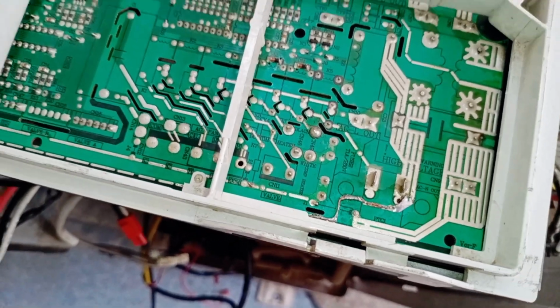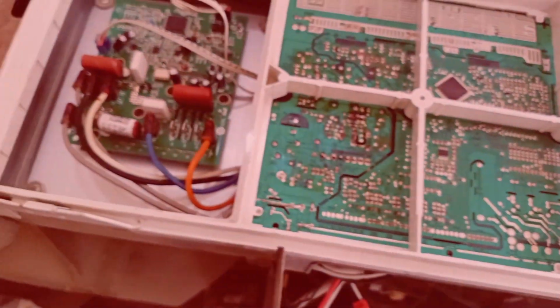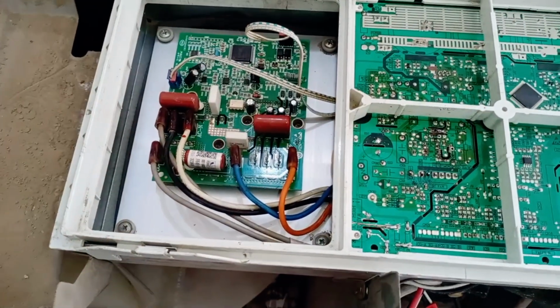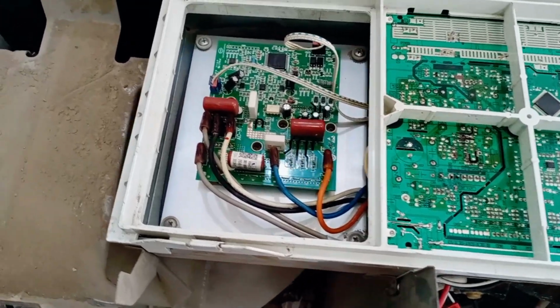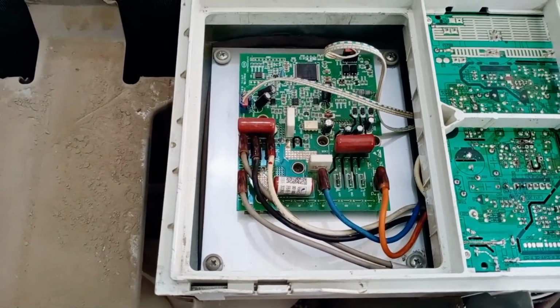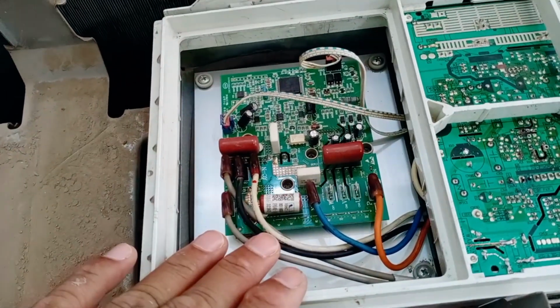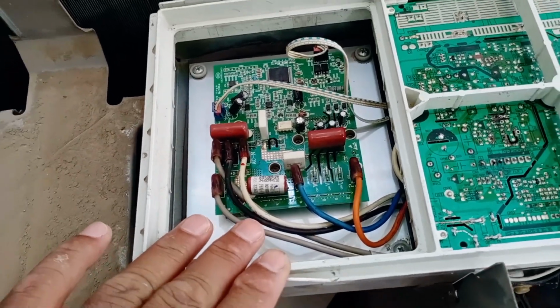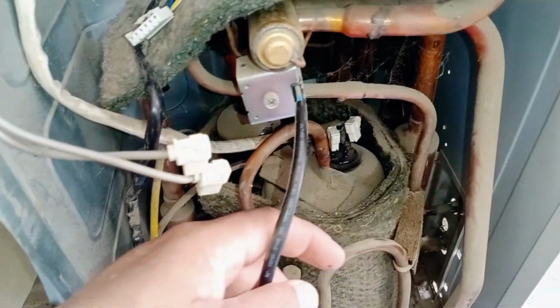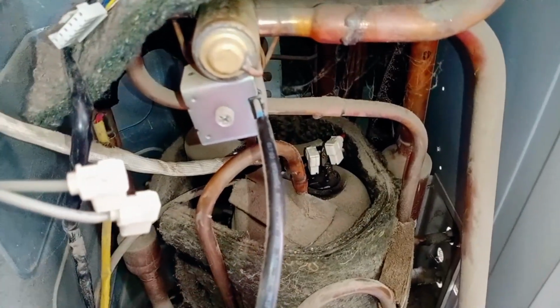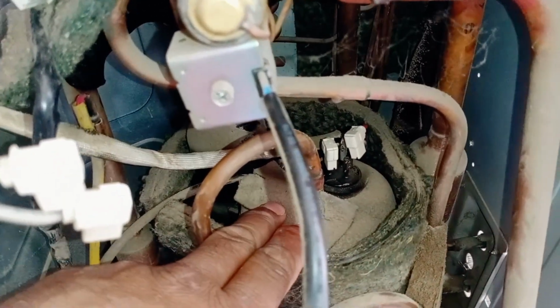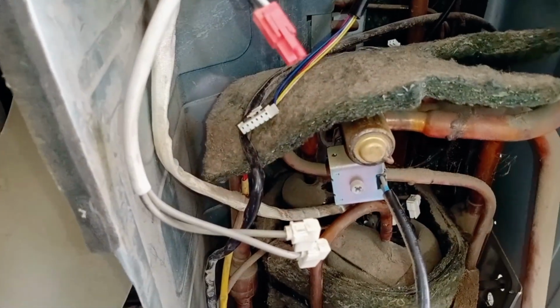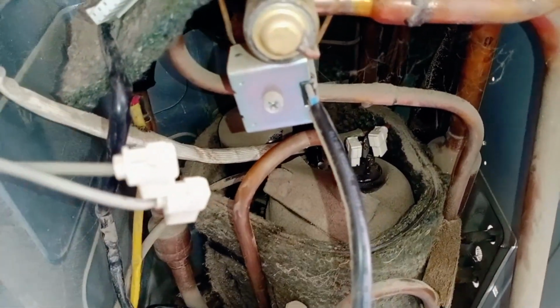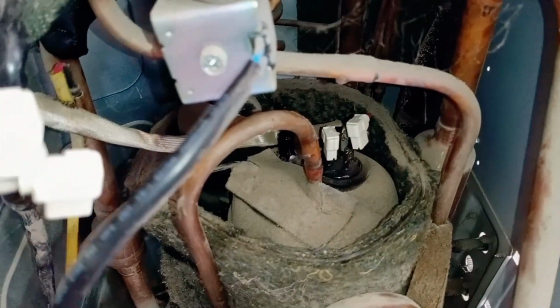After repairing, when I reinstalled the circuit board, we made a mistake. Or rather, it wasn't exactly a mistake, as I do check things properly, but as a human, sometimes errors happen. When I installed this circuit board back into the unit, I didn't check the compressor. If you don't check the compressor before repairing, the circuit board could develop issues again. And the same thing happened here. I had completely installed the circuit board and started the unit, but during this time, the circuit board failed again.